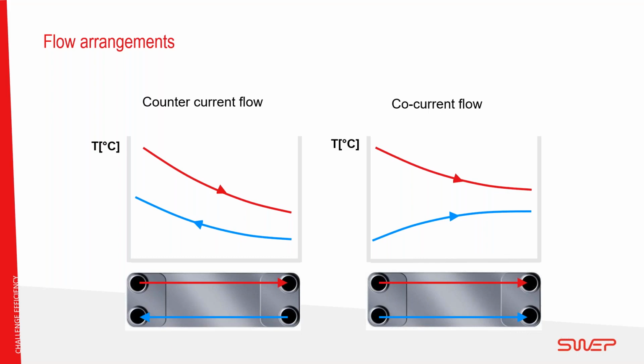This is found in the vast majority of applications we see, since it allows for an internal temperature cross of the two fluids. On the right, we have co-current, and this is where the flows enter at the same end of the heat exchanger and are therefore parallel. It's actually less efficient than countercurrent because the exit temperature of the colder fluid can't be greater than the exit temperature of the hot fluid.